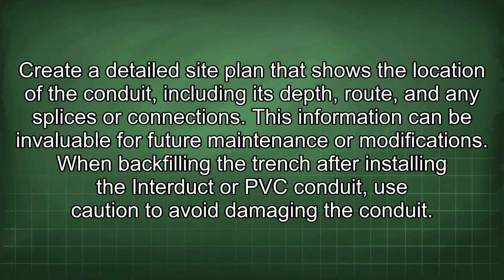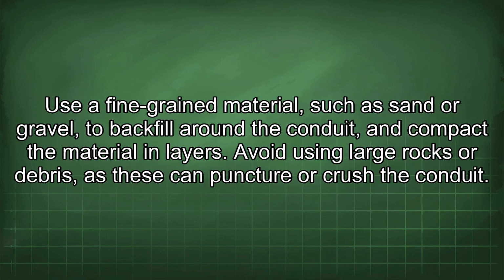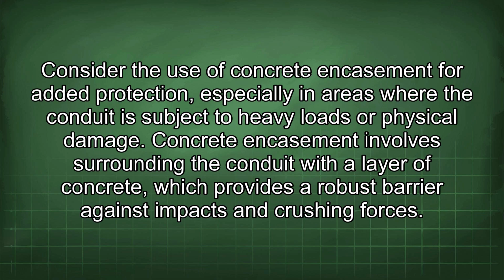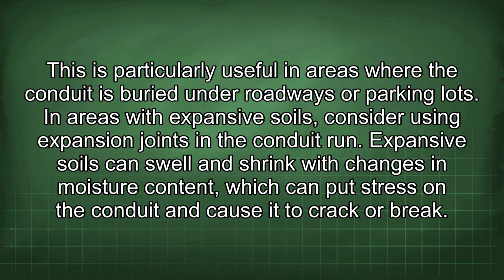When backfilling the trench after installing the Interduct or PVC conduit, use caution to avoid damaging the conduit. Use a fine-grained material such as sand or gravel to backfill around the conduit and compact the material in layers. Avoid using large rocks or debris, as these can puncture or crush the conduit. Consider the use of concrete encasement for added protection, especially in areas where the conduit is subject to heavy loads or physical damage. Concrete encasement involves surrounding the conduit with a layer of concrete, which provides a robust barrier against impacts and crushing forces. This is particularly useful in areas where the conduit is buried under roadways or parking lots.